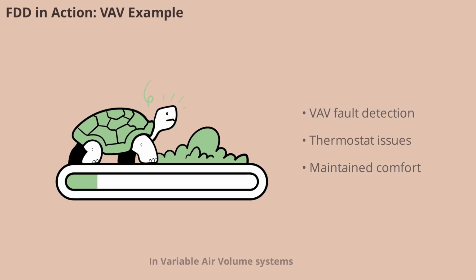In variable air volume systems, FDD can detect low zone temperatures even when the damper is open. The system may diagnose a thermostat miscalibration or actuator failure, allowing for precise corrective action. This level of detail ensures that comfort and efficiency are maintained.